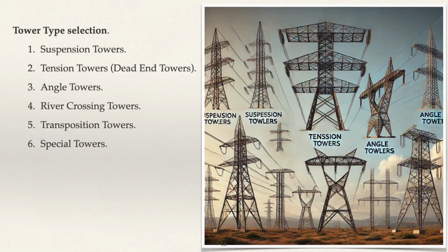Tower type selection. Choosing the appropriate tower type, e.g. suspension, tension, angle, or dead-end towers, based on factors such as voltage level, terrain and topography, line alignment and angle, environmental condition, span lengths, and conductor type, crossings and obstacles, safety and ground clearance. Proper tower selection is a key factor in the successful execution of a transmission line project, ensuring reliability, safety, and cost-effectiveness. 1. Suspension towers. 2. Tension towers, dead-end towers. 3. Angle towers. 4. River crossing towers. 5. Transposition towers. 6. Special towers.